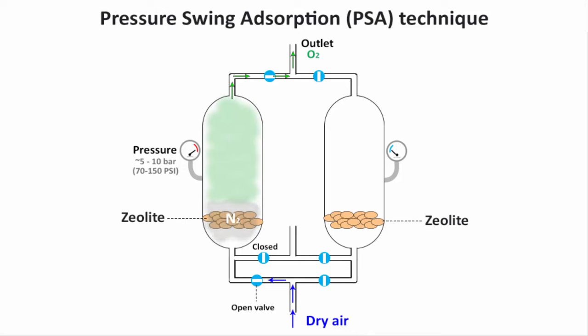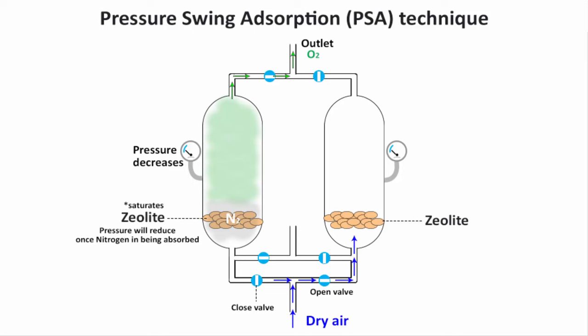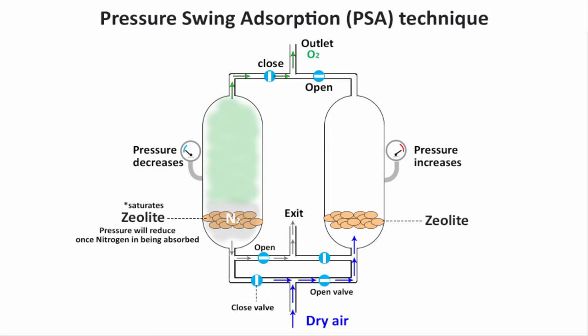While the first tank is removing nitrogen, the pressure in the first tank slowly reduces. Compressed air is then directed into the second tank by shutting the inlet of the first tank. When pressure decreases in the first vessel and the zeolite becomes saturated with nitrogen, the waste product is exhausted through the exhaust system. Simultaneously, pressure in the second vessel builds up due to incoming compressed air, and nitrogen settles down due to the presence of zeolite. This entire cycle is controlled electronically so that when the pressure of the first tank goes down, the pressure of the second tank will be up, and vice versa.